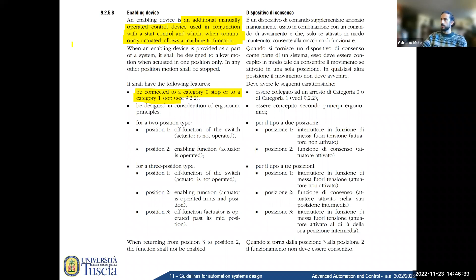Okay, so the second requirement is that a PLC program should be written so as to avoid accidental damage to property. So, interlocks between commands that activate different or opposite functions. For example, again, we have seen an example in one of the exercises we made. You might have a start-stop mechanism where you can have a short circuit if you press both buttons together. In that case, you can interlock them. So if you press one, you cannot press the other, and the same the other way around.